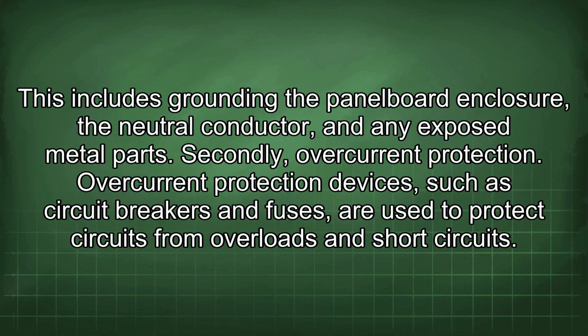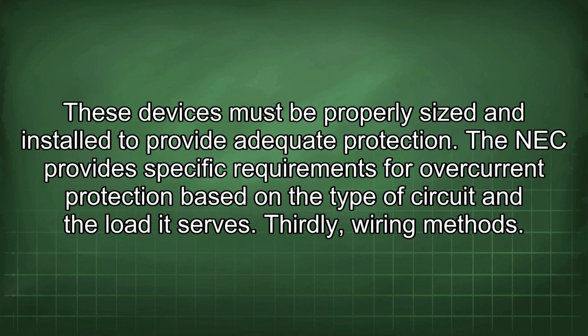This includes grounding the panel board enclosure, the neutral conductor, and any exposed metal parts. Secondly, overcurrent protection. Overcurrent protection devices, such as circuit breakers and fuses, are used to protect circuits from overloads and short circuits. These devices must be properly sized and installed to provide adequate protection. The NEC provides specific requirements for overcurrent protection based on the type of circuit and the load it serves.